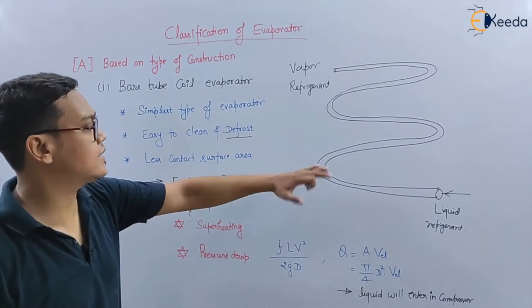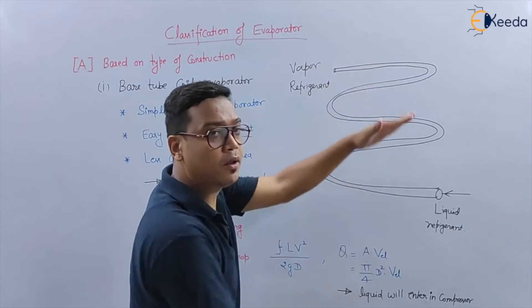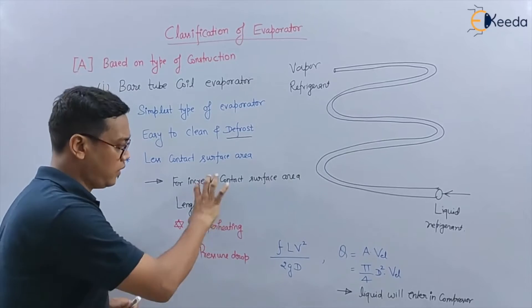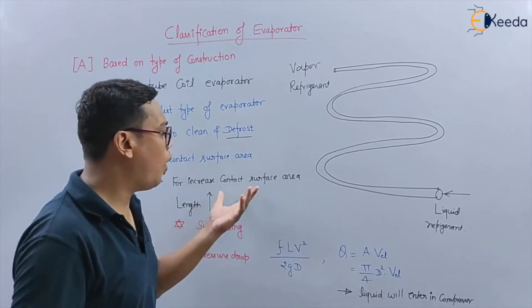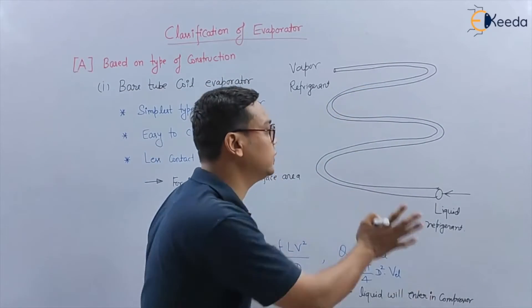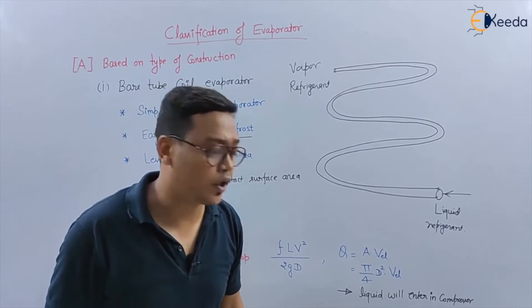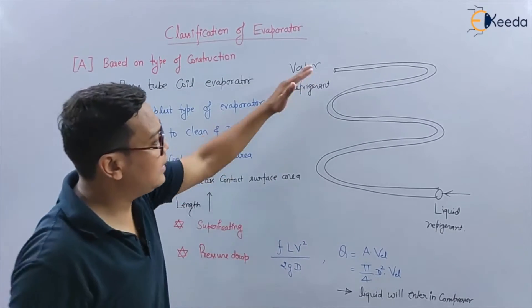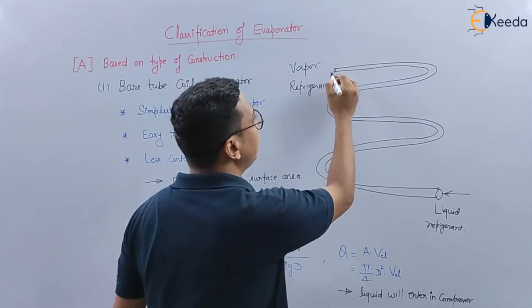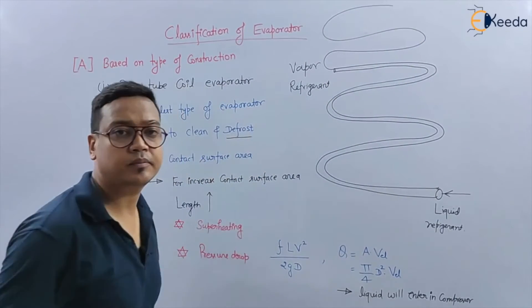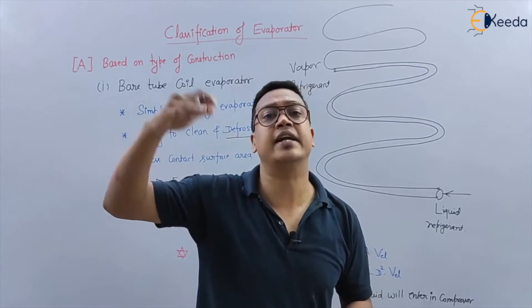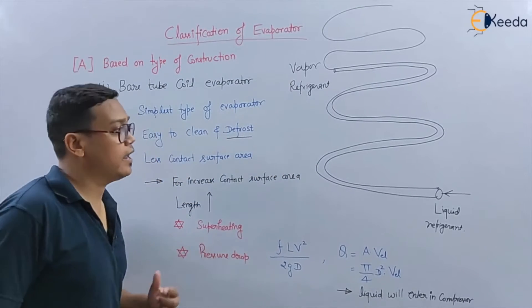You can easily see that the bare tube coil evaporator has less contact surface area because the spacing is low. If I want to increase the contact surface area so that maximum heat transfer can take place, I will increase the length of the coil. However, if I increase the length beyond a certain level, the first effect will be superheating of the refrigerant.